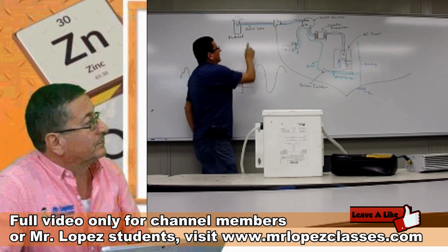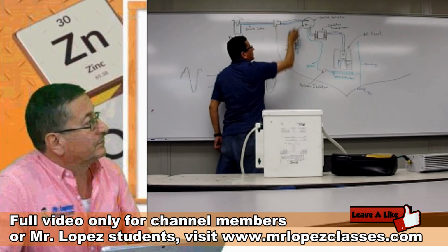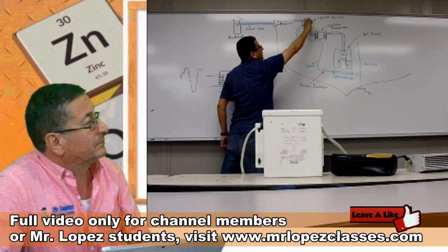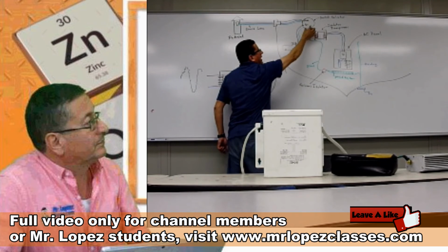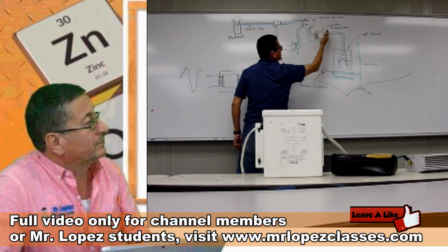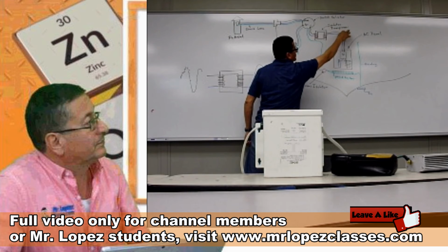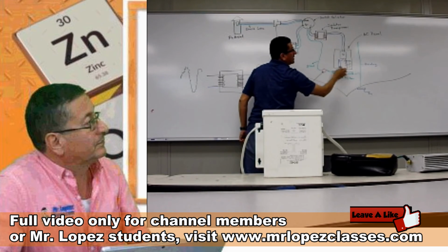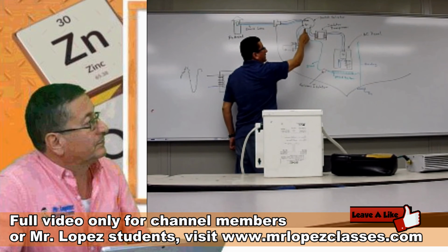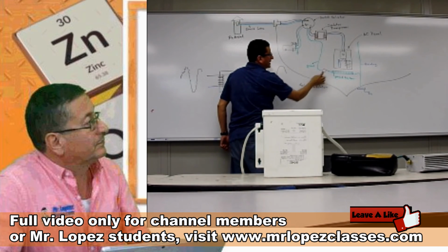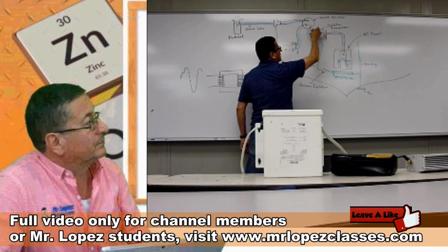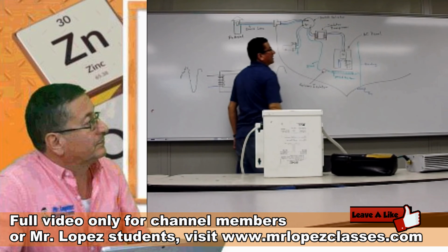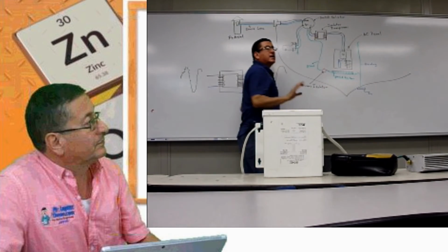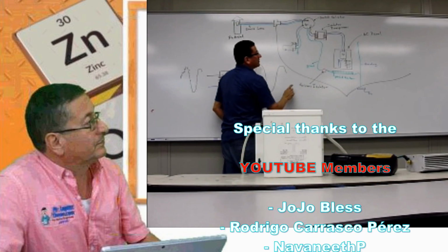Where is it located? This is the shore power entering the boat, or the power from the generator passing through the switch selector. You select generator or shore power, and from the common you insert the isolation transformer in series, hot line and neutral, and the output is the clean signal. The clean signal enters the main breaker of the AC panel. The ground is outside. In the ground you insert the galvanic isolator, and in the hot line and neutral you insert the isolation transformer. The function of the isolation transformer is to clean the signal, and the function of the galvanic isolator is to block the intrusion of bad currents through the ground.